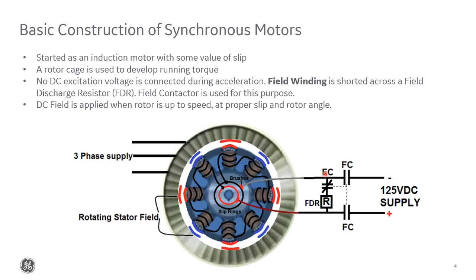So procedurally, we energize the stator as usual. The rotor typically will have some form of a lightweight squirrel cage so that it can catch that induced current and magnetize in that magnetic torque to start the rotation. Once that rotor comes up to speed, as it would in a normal induction motor, usually somewhere around 95% speed with a 5% slip, then we close in this DC excitation system. We open the series field contactor, and then that DC supply is closed in and provides that extra little bit of torque to eliminate the slip, and it locks in the rotor to the stator. And then again, moving forward as required, the DC supply can be adjusted to maintain synchronism or to allow for other conditions, which we'll touch on in a few minutes.